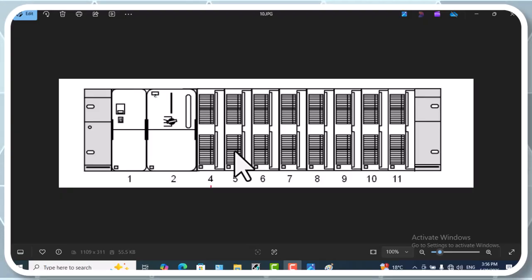For digital input and output modules, Siemens reserves 4 bytes of addressing space per slot. And why 4 bytes? Because 1 byte is 8 bits, and the system reserves 4 bytes for each module, and a typical digital module can have up to 32 channels. And how do we calculate the address? Let's take a look at the formula now.